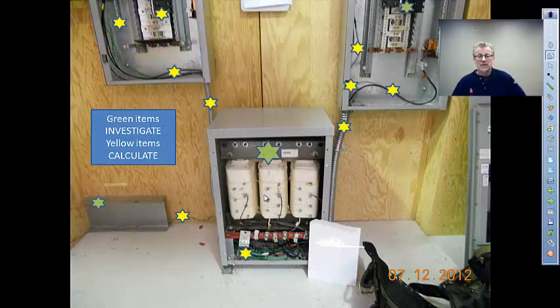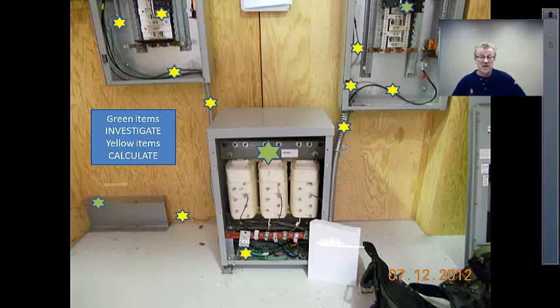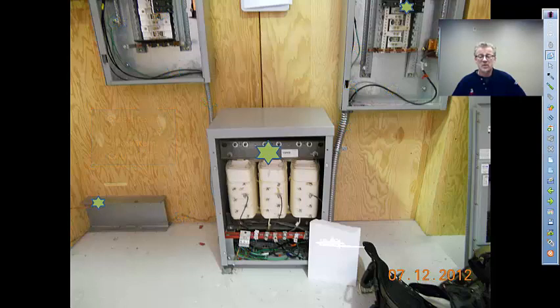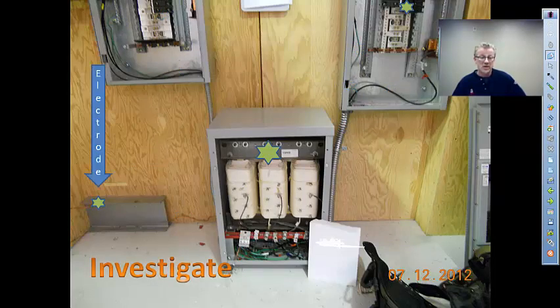We will go either on blueprints or physically in the field, look at these green items, which will give us the information necessary to calculate all of the yellow items. Those green items that we're going to investigate include the grounding electrode system. Might look on the plans and specs, might go look in the field. A metal underground water pipe or building steel frame building, which is grounded, will drive us directly to Table 250.66, and that's what we'll do today. Go directly to Table 250.66. Of course, these grounding electrodes have to be bonded together in order to create a grounding electrode system. That's another discussion.